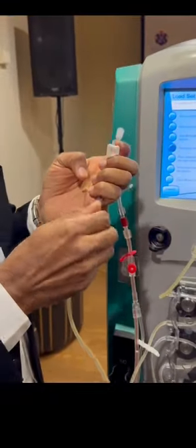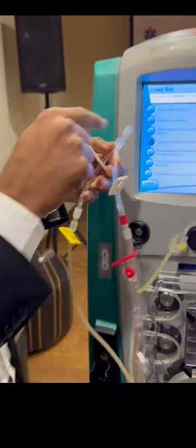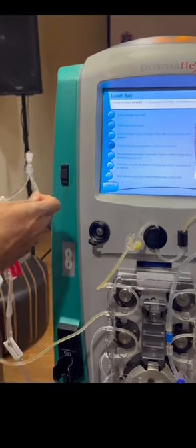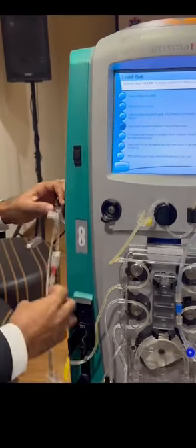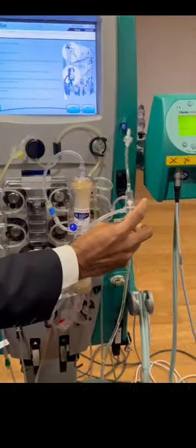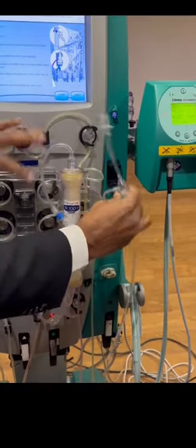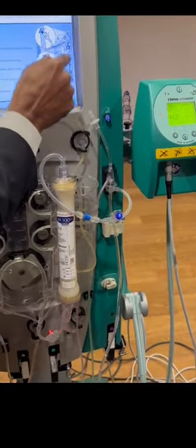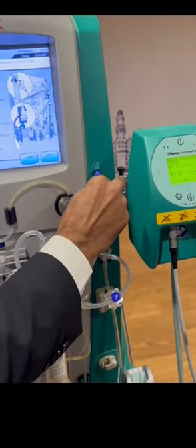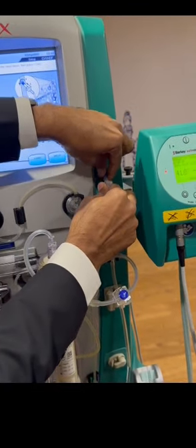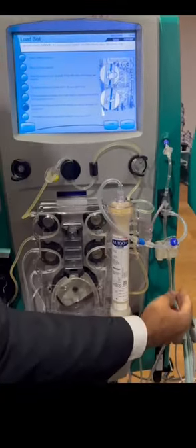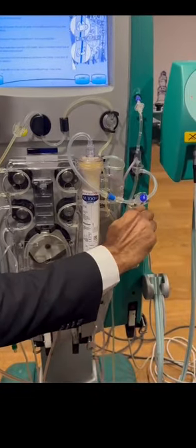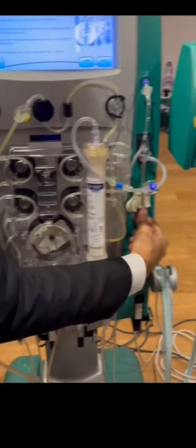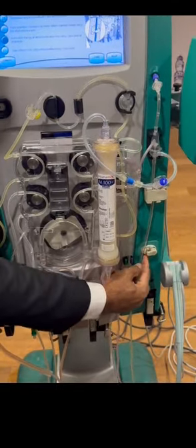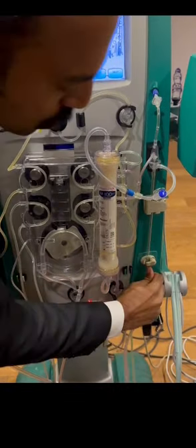In HD also they have one white color connector. Instead of that we have this Y connector. Next, connect the deaeration chamber. This is the deaeration chamber, to deaerate the circuit. I kept it here like this. Then the return pressure port. Then insert it in the air detector. How to open it? Just press it, and you can remove it. Then this is the clamp, in case the air detector needs to stop further flow.